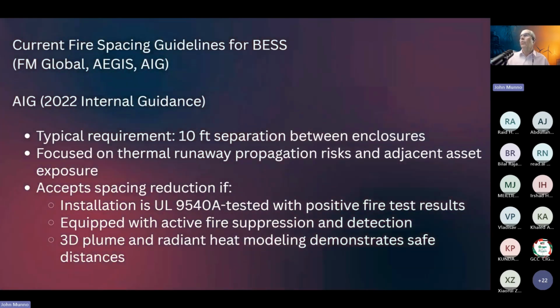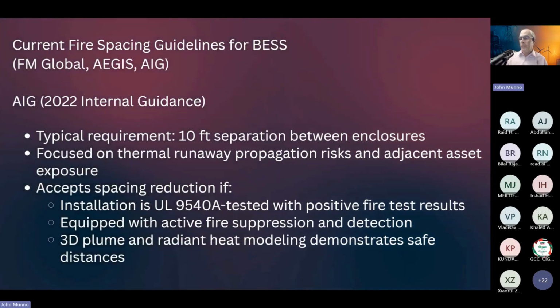AIG, they're much more reasonable. They would like 10 feet of separation. 10 feet is what even the manufacturers who have tested to 8 feet suggest. So Wärtsilä has done some full-scale testing, and their testing suggested that at 8 feet, there's not a huge risk of propagation from container to container. But they say that they recognize that you need about 10 feet just for maintenance activities. So with that, they're about the most reasonable, and 10 feet seems to be what all the following markets like to see as well.